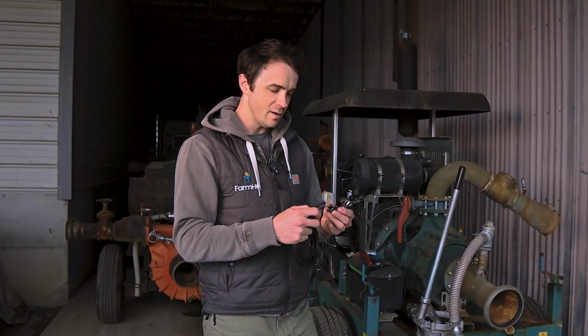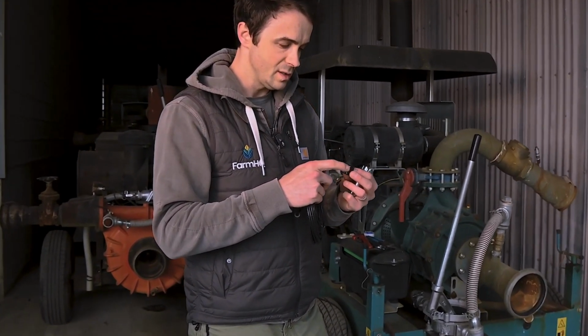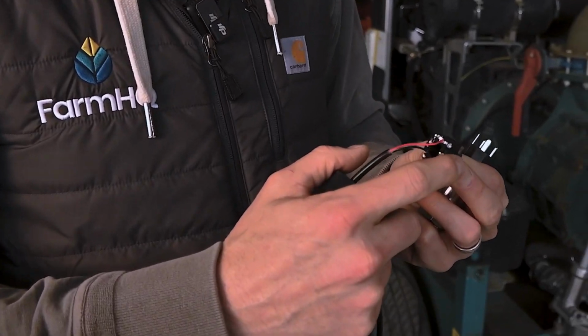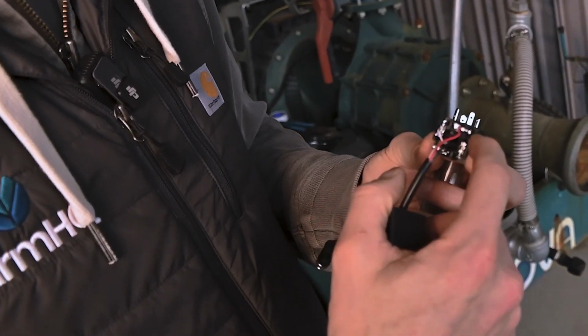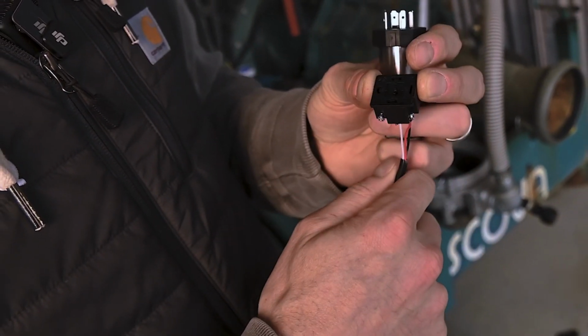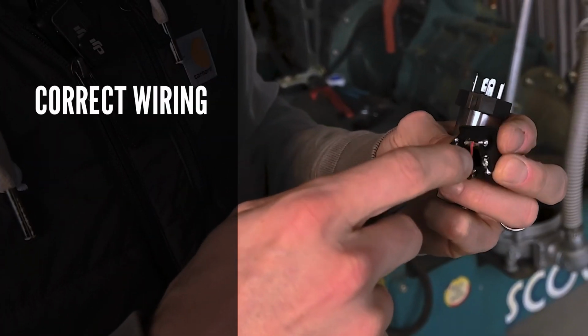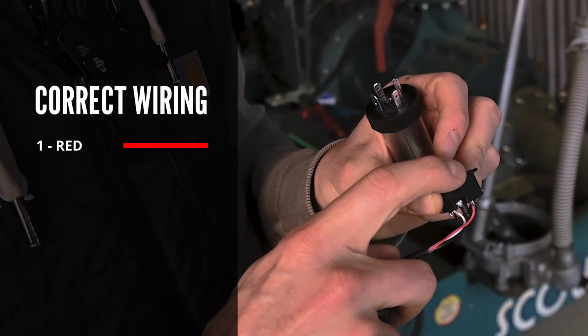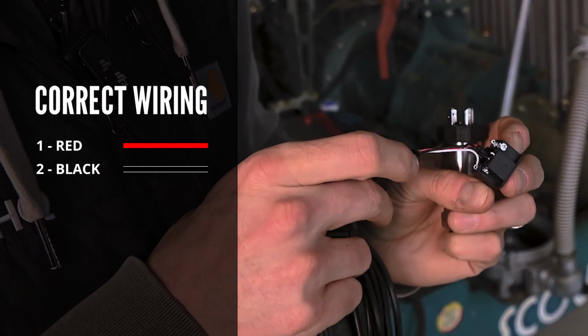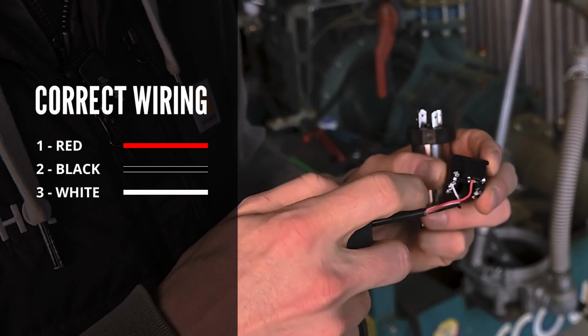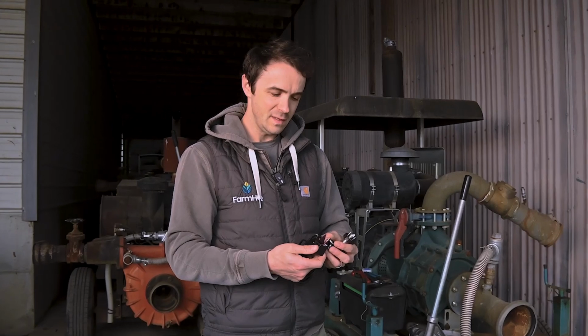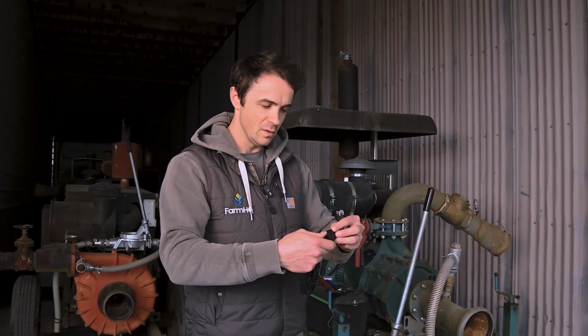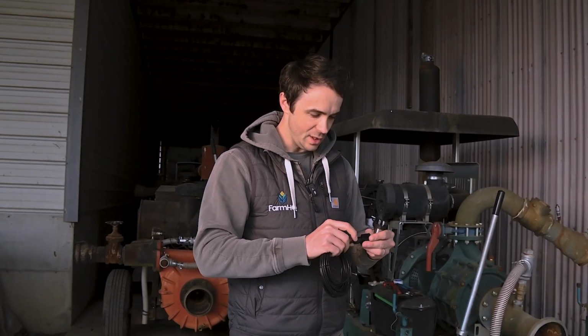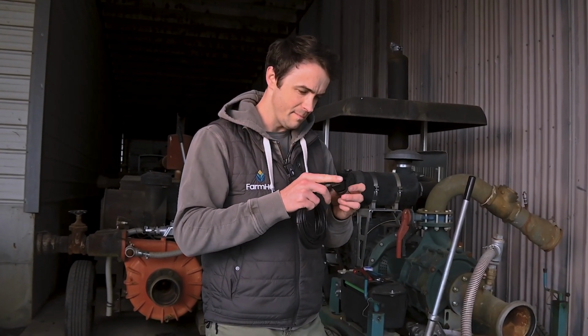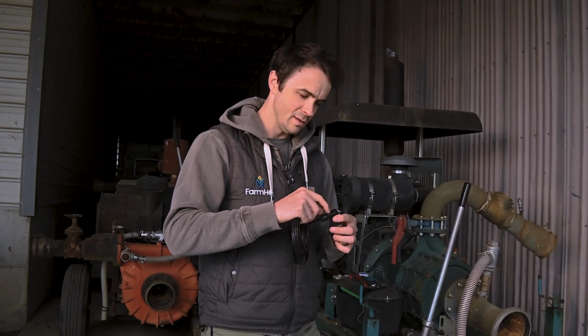The correct wiring on these Hirschmann connectors you can determine by looking at the numbers on the terminals. So the numbers are located on the front side of the terminal and also on the back side. In order to wire these up, you're going to connect the red wire to terminal number 1, the black wire to terminal number 2, and the white wire to terminal number 3. Once you've got that wired up, you can go ahead and close up the connection and secure the cable nut onto the cable.